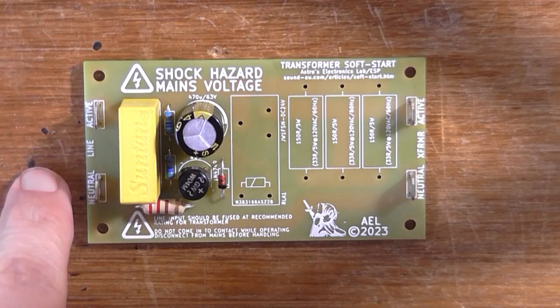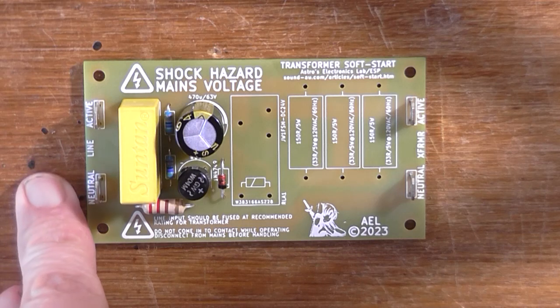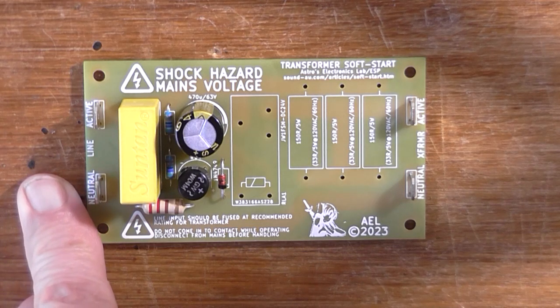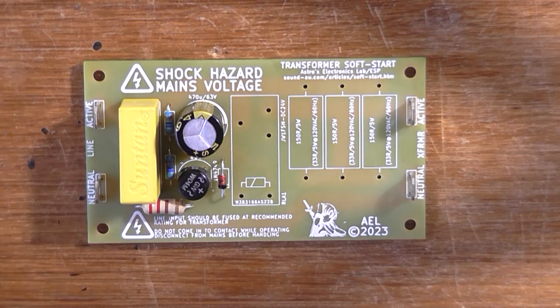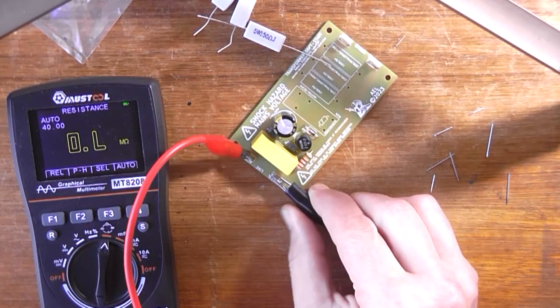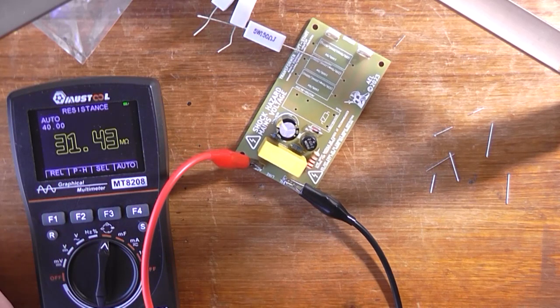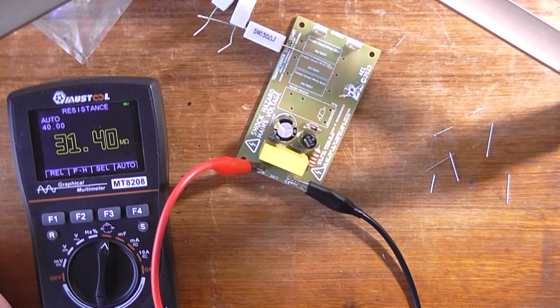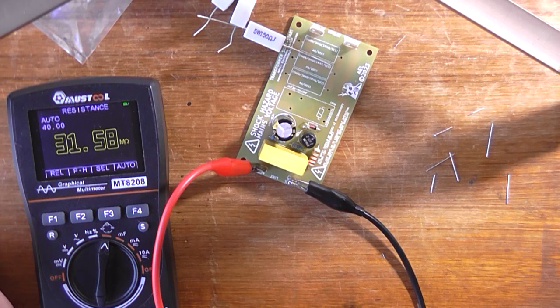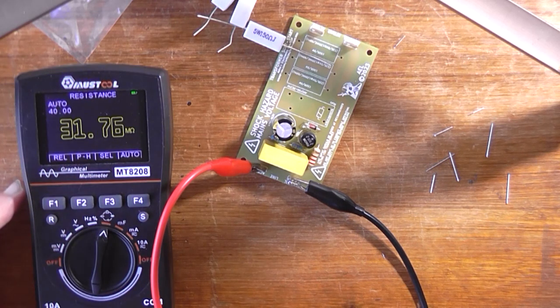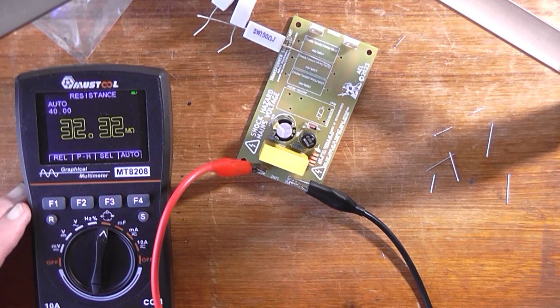I'm going to measure the resistance across that input, because it shouldn't be short-circuited - that's not how the circuit works. The other lead there. And we've got mega ohms, so that's going to be perfectly fine to connect up to the line without causing any issue like blowing circuit breakers, but I'm still going to put it through a dim bulb tester just to be 100% sure.